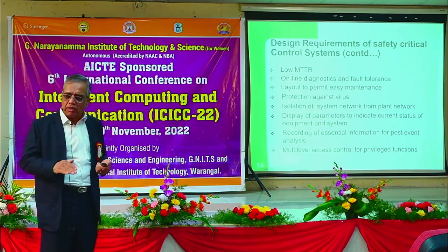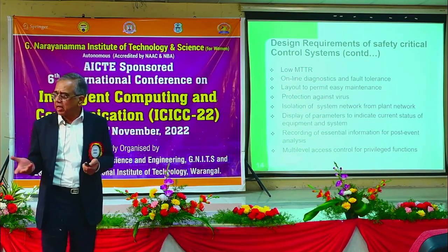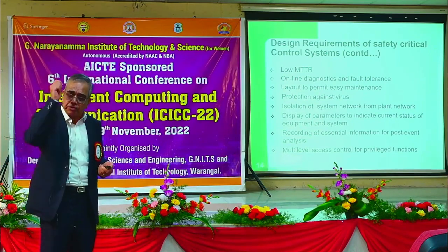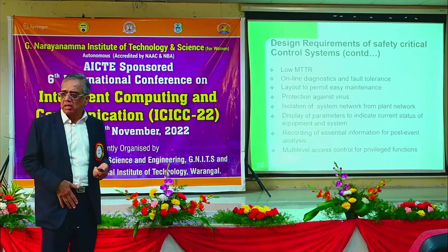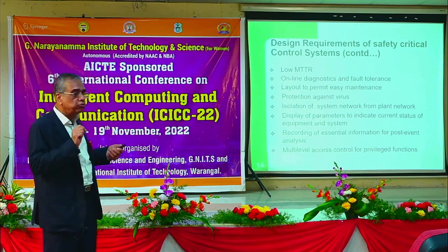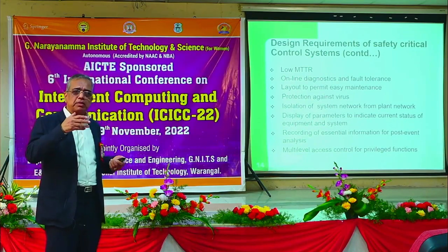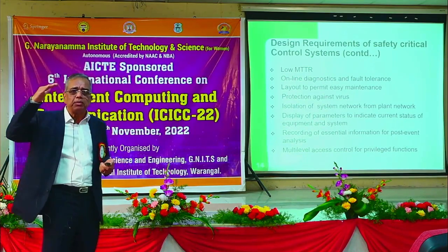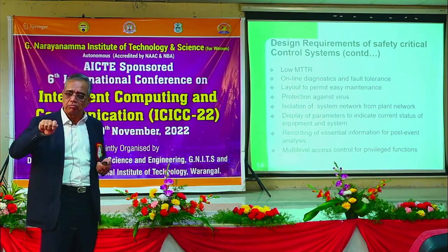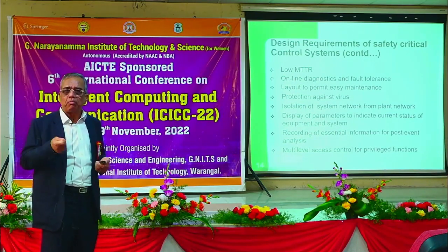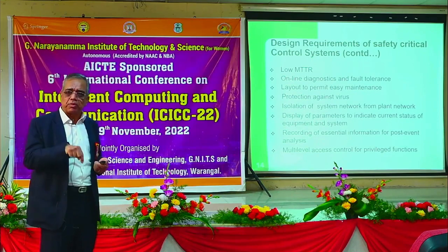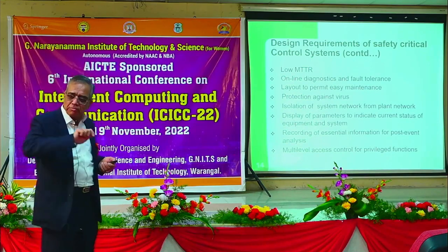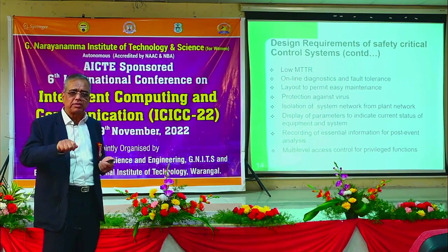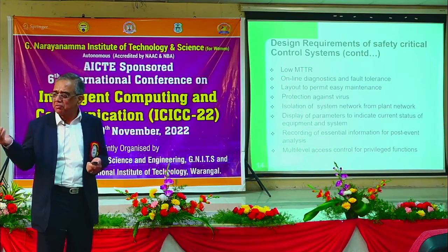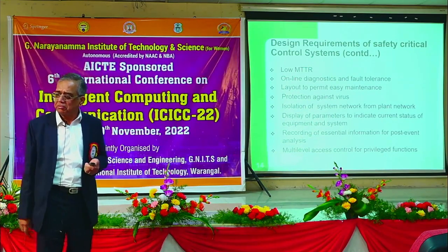Different operators will have different levels. One will be able to change some parameters, like PID constants, the first time he is trying to tune the system, or some parameters which can be changed by, let us say, the shift charge engineer. There he has to have a key to operate, a mechanical key, and also the password. When you turn the key, a particular digital input will become true, and only then will he be able to do this.